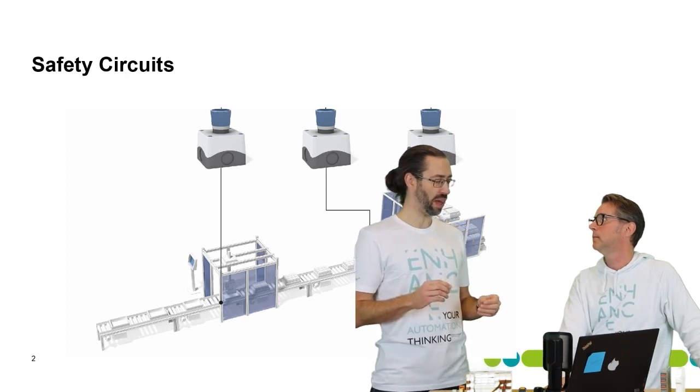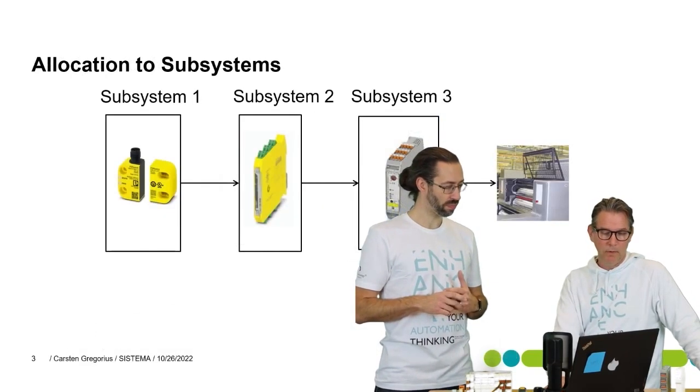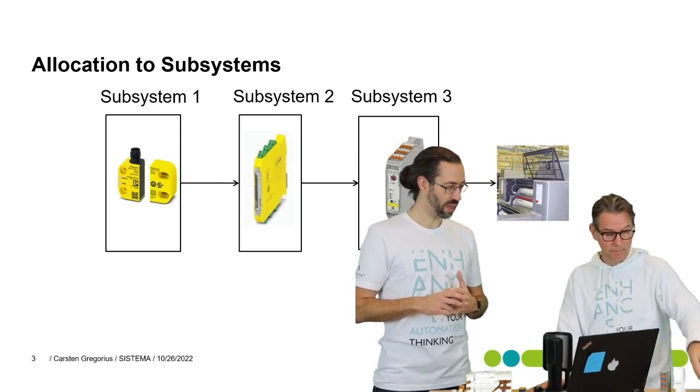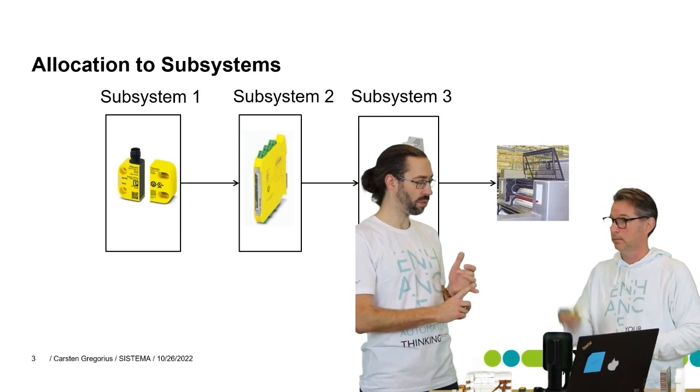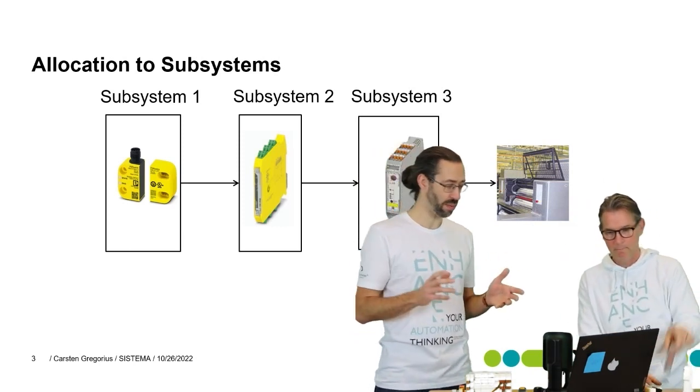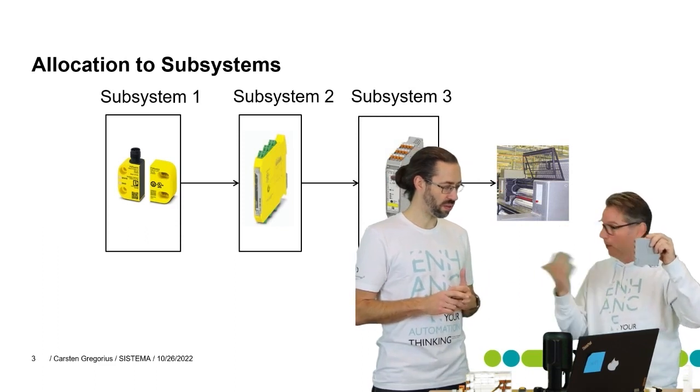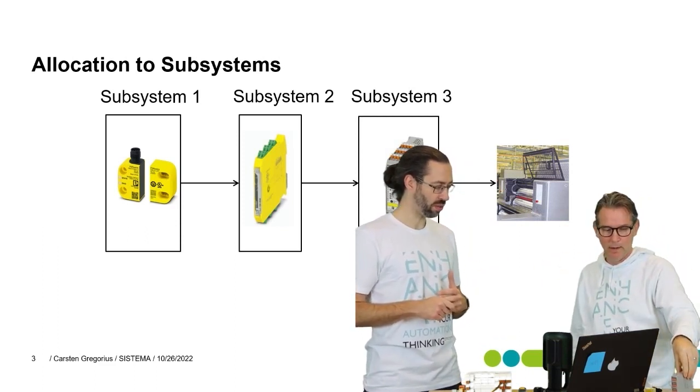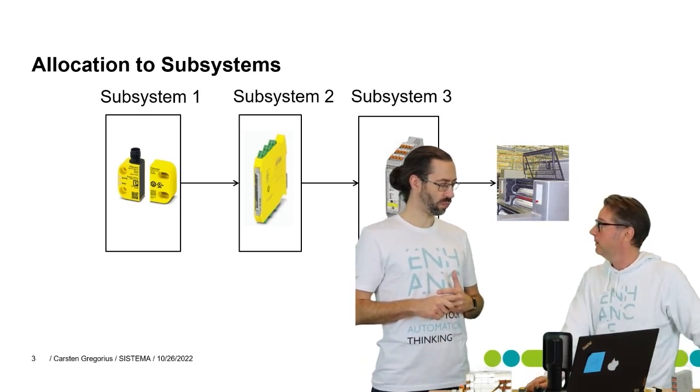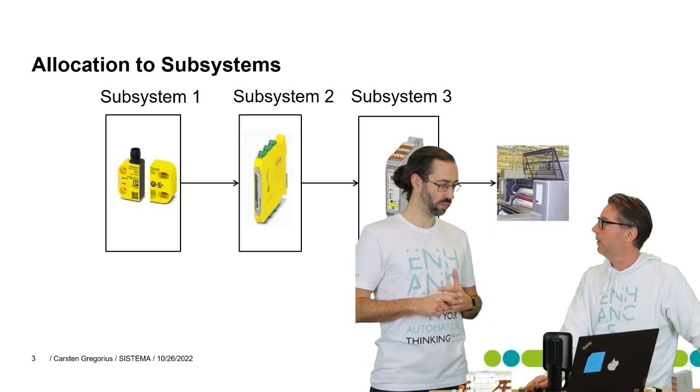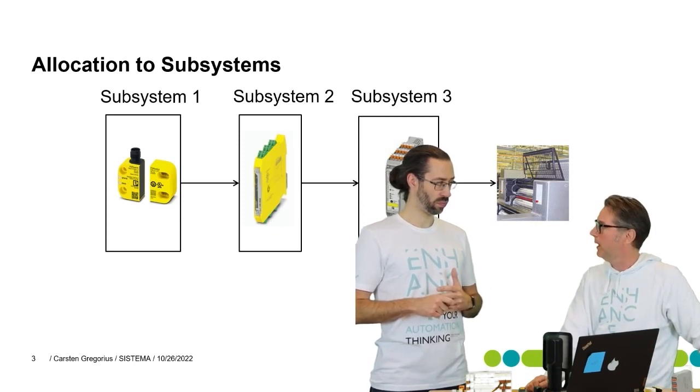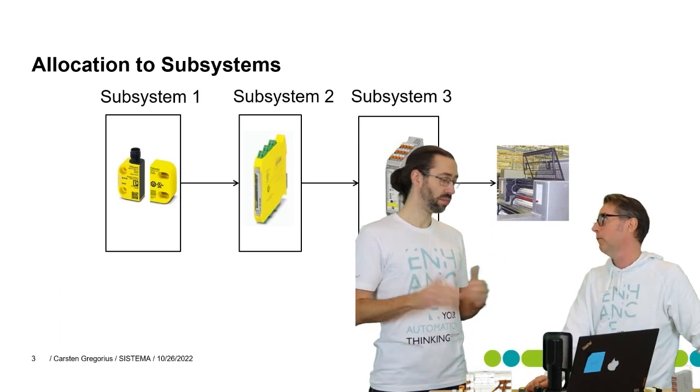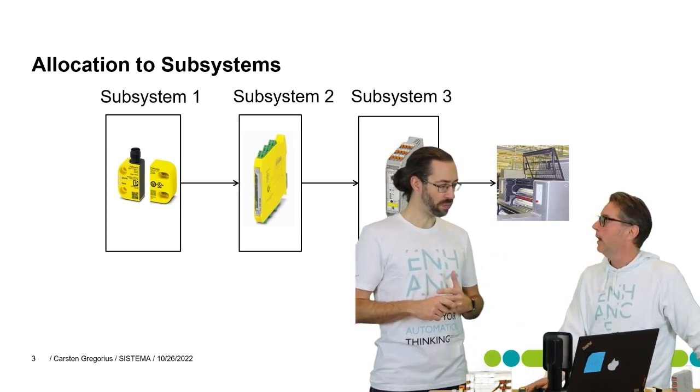We will look at one safety function for a machine as an example and see how this could be realized in SISTEMA. Here we have a safety function - it consists of three subsystems: input, logic, and output. Three different parts, that's one of the simplest versions. Here we do the risk assessment and in our case we have come to the conclusion that PLD is something we want to achieve.